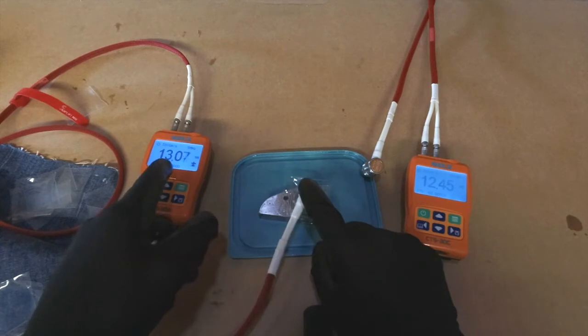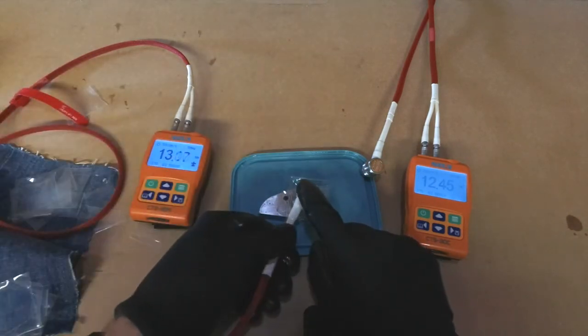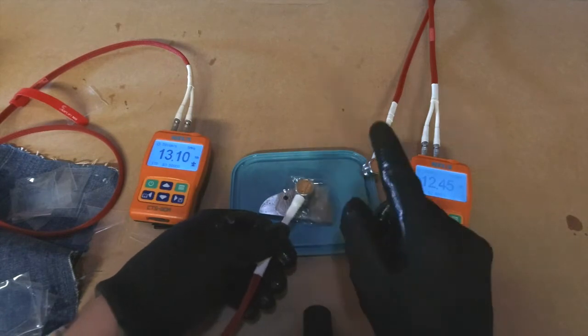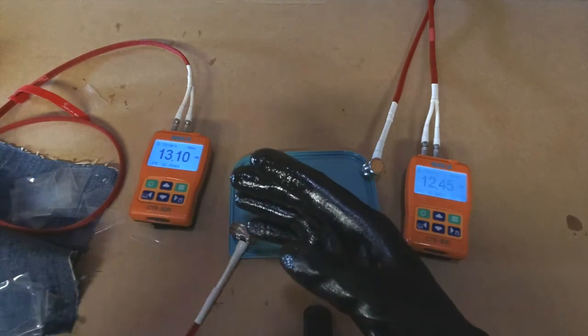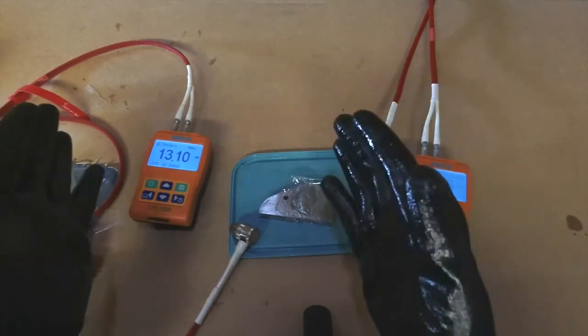So approximately change the thickness by 0.6. Okay, so this unit has already gone from 12.5 up to 13 millimeters. Now, that's because this unit, the way this thinks is, where the probe and the interface of the probe and the material, it's calculating the time to the first echo, and giving the reading from that perspective.